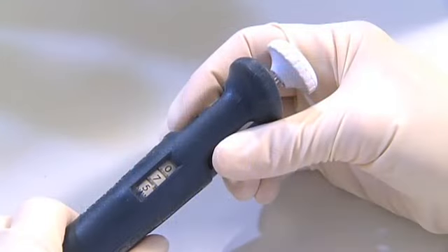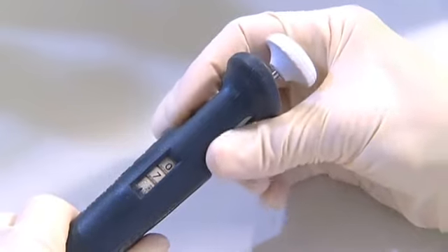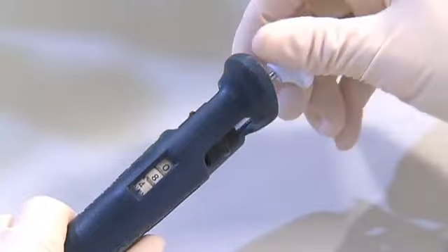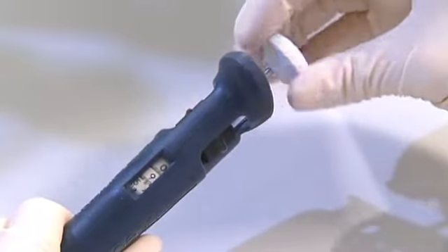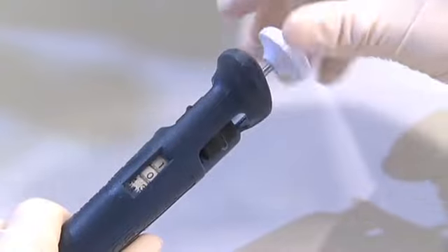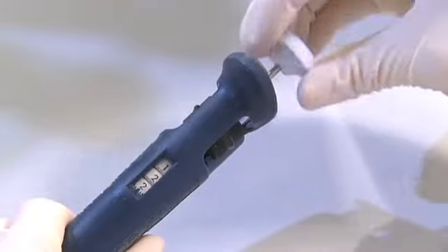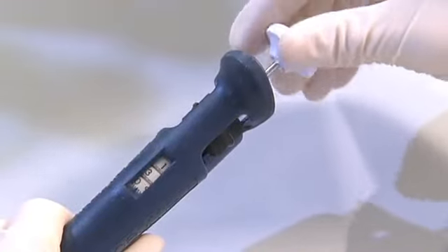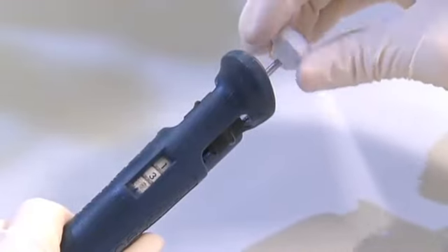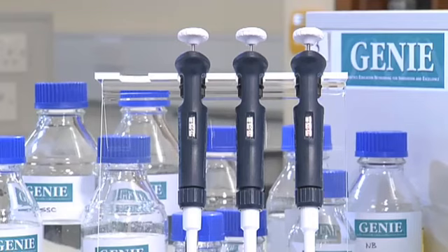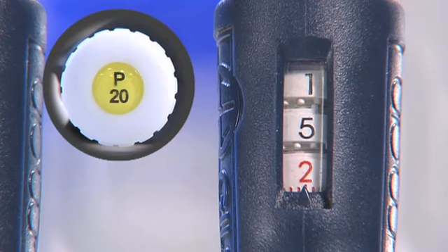Each pipette has a vertical row of 3 numbers visible in the body of the instrument. To set the volume, you can use either the thumb wheel or, on newer models, the push button. This will cause the 3 number dials in the body of the pipette to rotate and change the volume of liquid that will be taken up. However, the dial numbers indicate different volumes depending on which pipette is used. For example, these pipettes have been set to read the same numbers on the dial, 152.